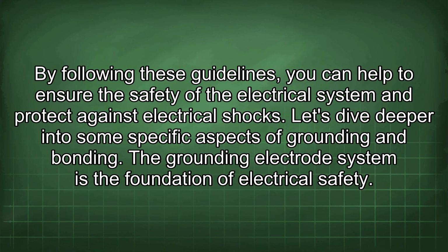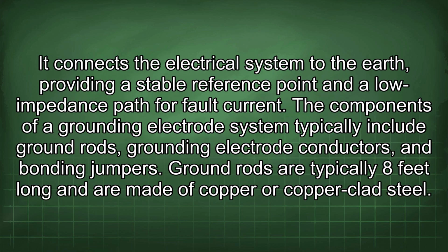By following these guidelines, you can help to ensure the safety of the electrical system and protect against electrical shocks. Let's dive deeper into some specific aspects of grounding and bonding. The grounding electrode system is the foundation of electrical safety. It connects the electrical system to the earth, providing a stable reference point and a low impedance path for fault current. The components of a grounding electrode system typically include ground rods, grounding electrode conductors, and bonding jumpers.